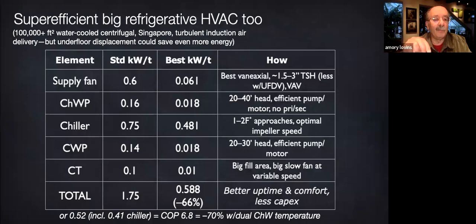Now, the Singapore wizard Lee Eng-lok and his protege Peter Rumsey routinely triple the efficiency of big new water-cooled centrifugal systems, shifting design power intensity, that is kilowatts per ton, for each major component from the second column to the third column, and by means explained on the right in the how column. And the total capital cost goes down, comfort and reliability go up. Now, exceptionally, let me do this chart in barbaric units. I will add it in metric in the PDF right after this slide.